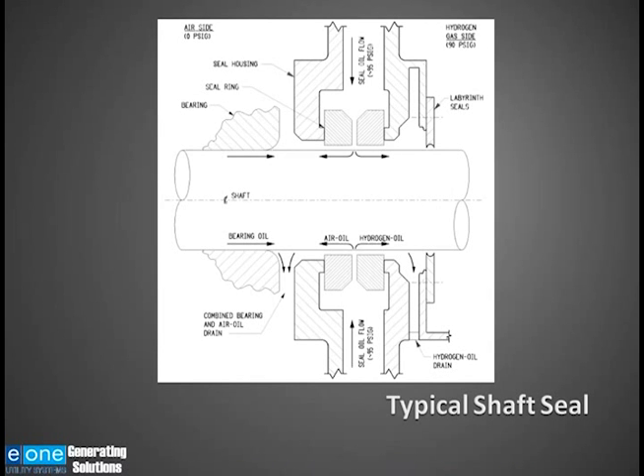This is a sectioned view of a hydrogen seal. Oil is used to seal the hydrogen in the generator and keep air from entering into the hydrogen. You can see from the top and the bottom of this slide where the seal oil is fed to the rotor shaft at 95 psig. This is a higher pressure than the hydrogen case pressure, which is 90 psig. So the seal oil will flow in the direction of the hydrogen and also in the direction of the air, creating an effective seal, keeping hydrogen in the case and keeping air out of the generator.